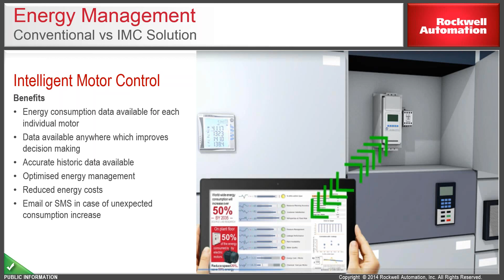So this is typically an architecture which we are showing on Ethernet IP. Down the line, if you see, there are various motor control devices. We have Ethernet relays, soft starters, variable speed drives, and motor control centers, and all are connected on the Ethernet IP network. Then these devices become intelligent devices, giving real-time information to the controller. And then on the top, it is going to the information layer or enterprise level, right?